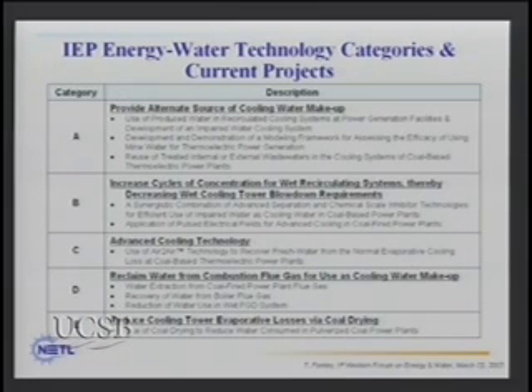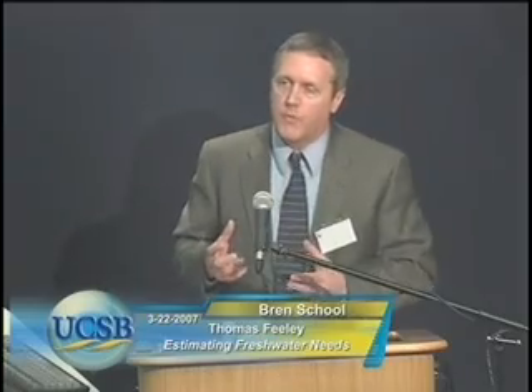And that takes a little thought, but the idea is to take the hot water that's returning to the cooling tower and run that through a heat exchanger to dry high moisture coals. So you're going to recover moisture from the coal and use that. You're also going to reduce the temperature of the hot water returning to the cooling tower, and you may be able to reduce some of the evaporative loss because the water going to the cooling tower is a little bit cooler than it would normally be.